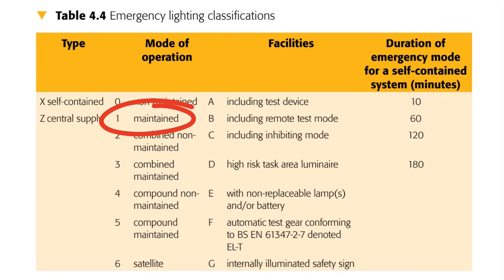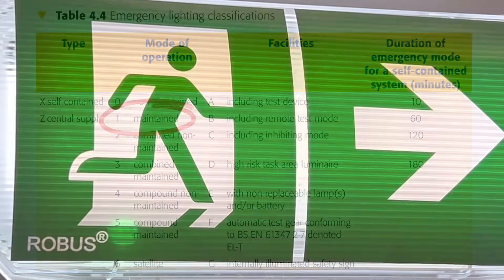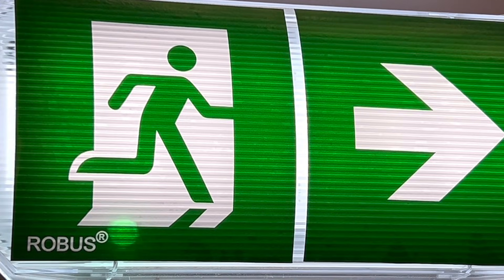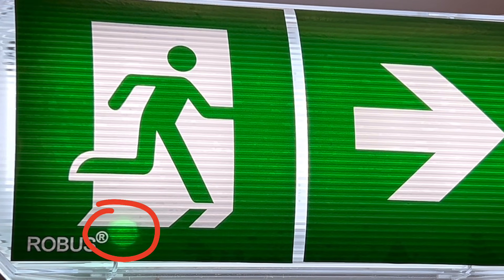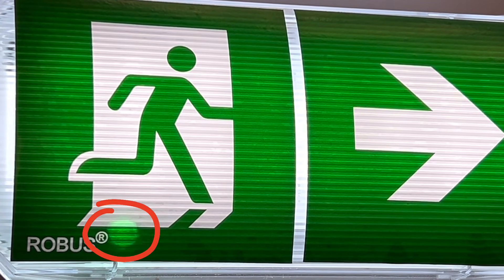Mode one is maintained. This type of emergency light is on at all times, so if the power supply to the fitting is healthy and all is well, the light will be on. If the circuit feeding the fitting fails for some reason, the light will remain on, but now being powered by the internal battery.